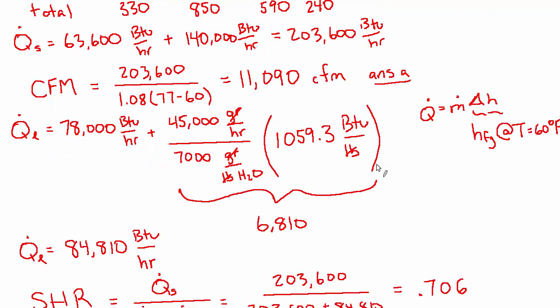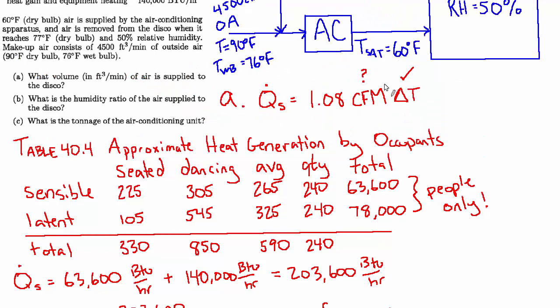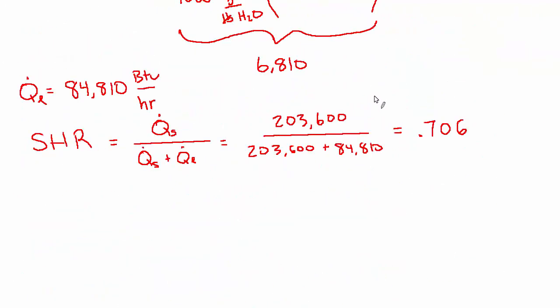But getting back to their question, which is what is the humidity ratio of the air supplied. So now we want to use this formula: the mass of water vapor that needs to be removed is equal to the mass of air that's being supplied times the difference in the humidity ratio. So in this case that's the humidity ratio in the room minus the humidity ratio of the supply air. So the humidity ratio in the room we can easily look up from the psych chart because we know the temperature and humidity in the room. We don't know the humidity ratio of the supply air—that's what we're looking to find out. We know the mass flow rate of air because we just calculated the volume flow rate in part A, so we can easily turn that into a mass flow rate just by using the density or the specific volume.